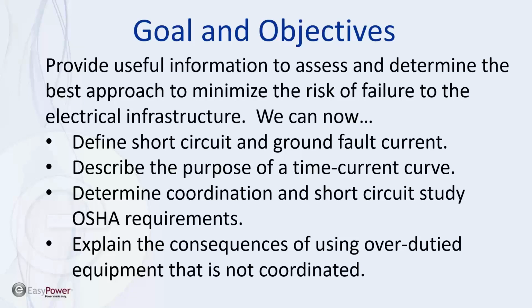You've got to read the study, because the engineer will put recommendations that this is over duty, this is over duty, there's an NEC violation, and they're now in writing to you to tell you what the hazards are, and you need to fix those. And if you don't fix those, then you're still going to be on the hook. Just doing an arc flash study is not enough. Make sure facilities people understand that if there are recommendations that need to be done, then they need to be done.